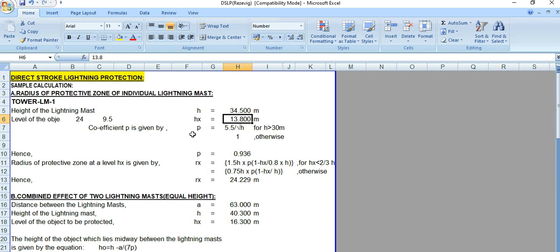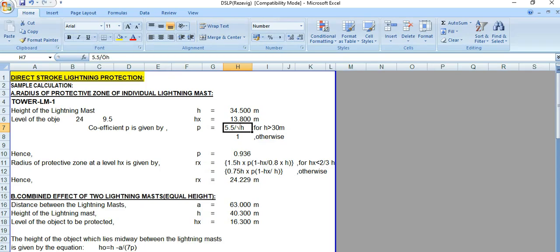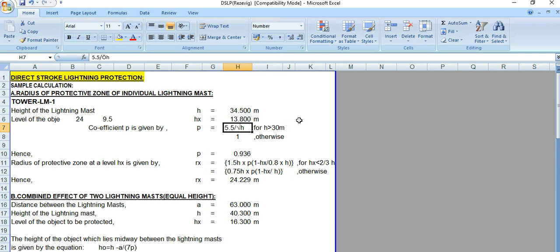The coefficient p is given by p equals 5.5 divided by the square root of h, applicable when h is greater than 30 meters; otherwise the value is 1. Since the lightning mast height is 34.5 meters, which is greater than 30 meters, we apply this formula. The resulting coefficient p value is 0.936.